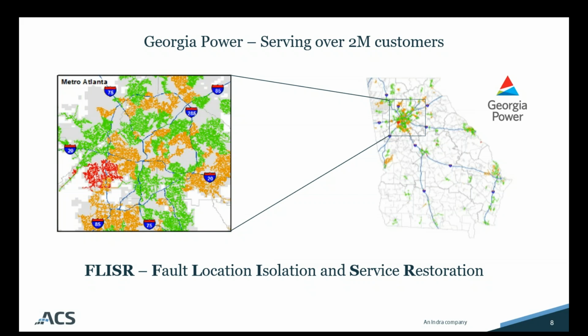The key goals of the project were to overcome the uncertainty of what might happen in an outage condition by deploying the best self-restoring technology possible. In short, identify and isolate faulted line segments and restore service to customers on unfaulted line segments: fault location, isolation, and service restoration. So we'll shorten this going forward for the rest of the webinar and call this FLISR.